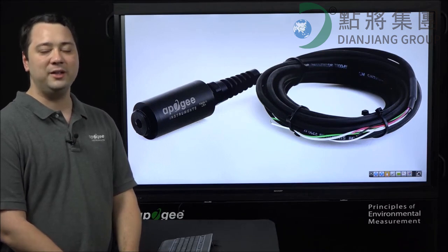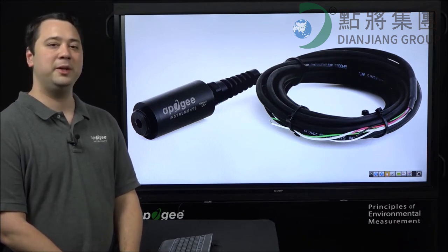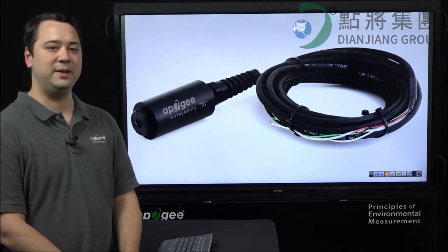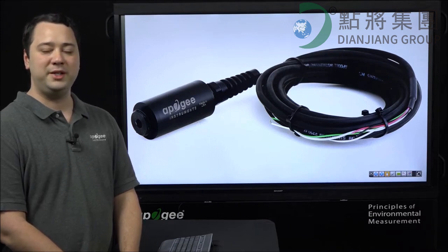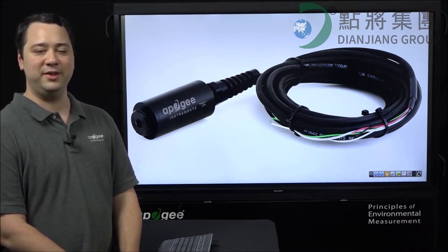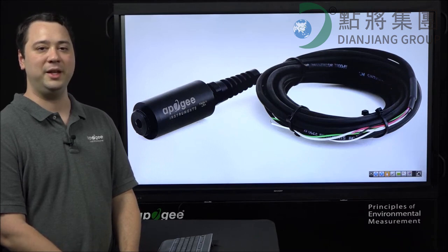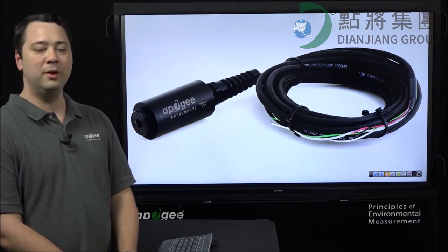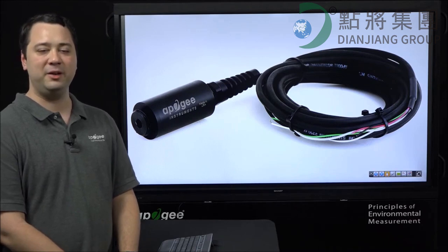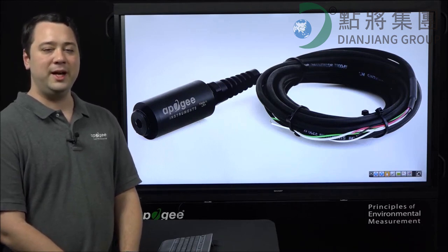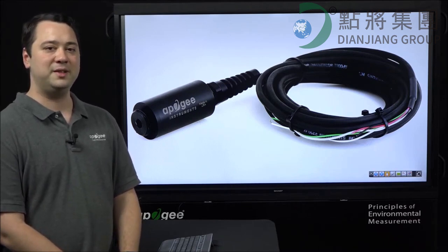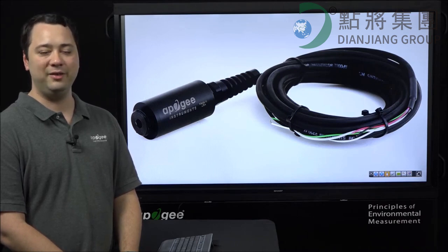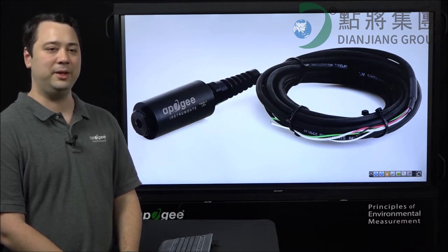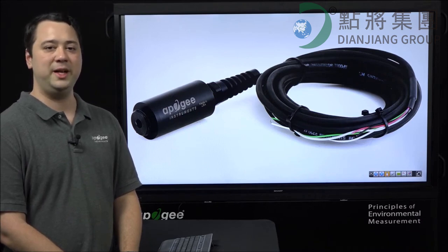So to calibrate it, you'll first want to set it up in an open air environment with a similar temperature, pressure, and humidity level as the sampling environment that you will be operating the sensor in. Once you've got it set up in this environment, you will want to let the sensor's millivolt readings stabilize, and then once they have, you will want to write down or record this millivolt reading as your calibration millivolt reading.